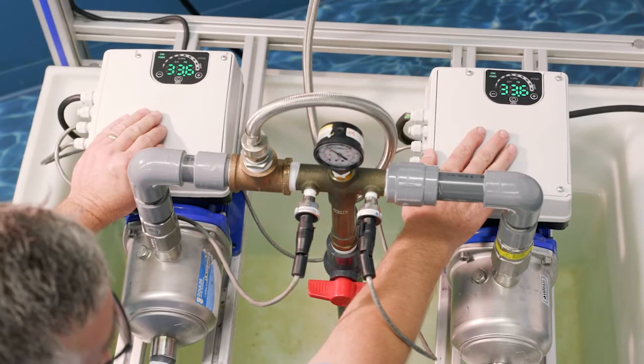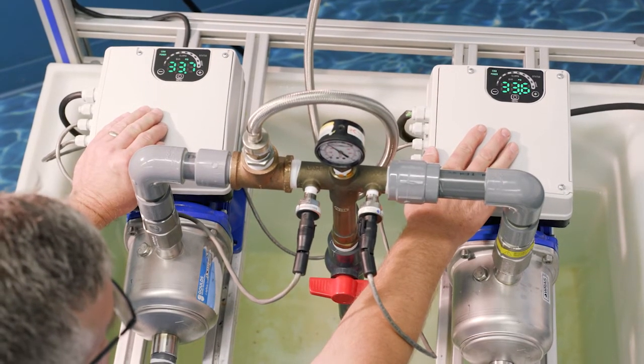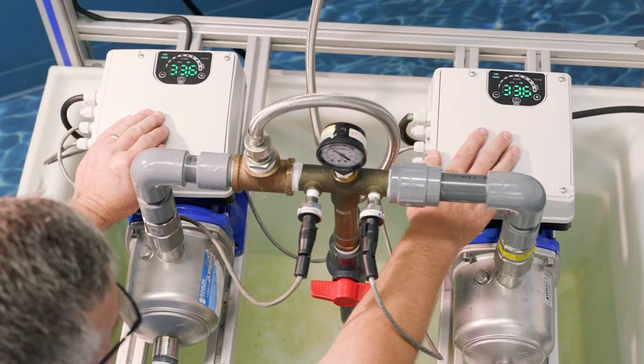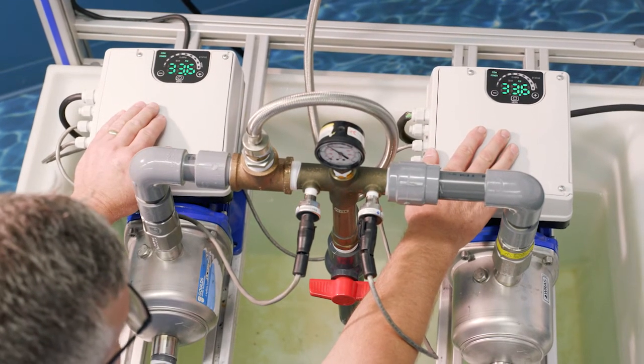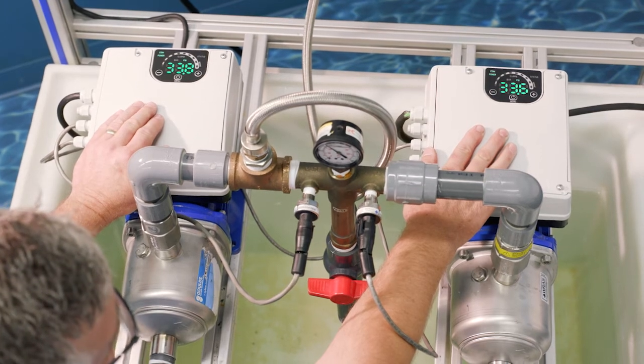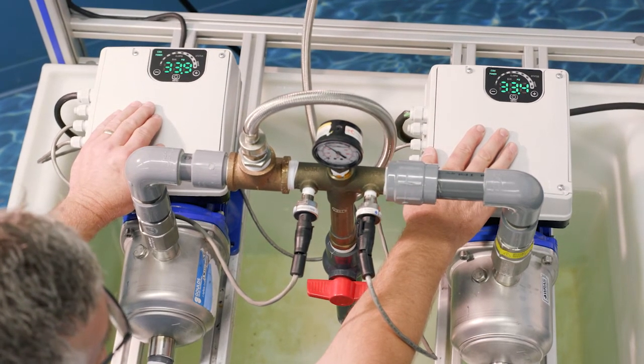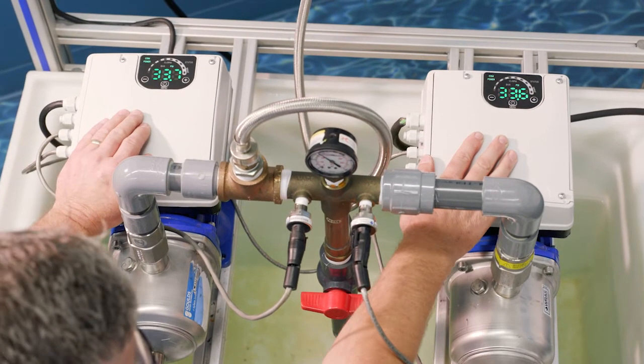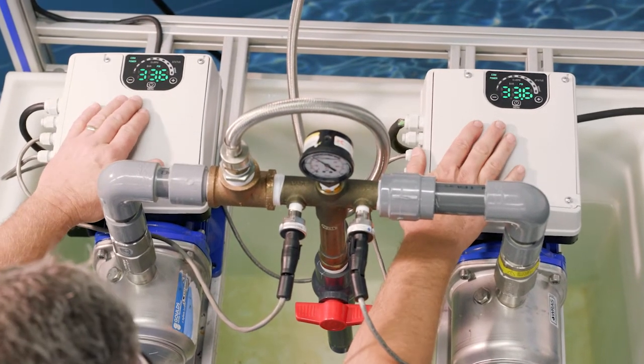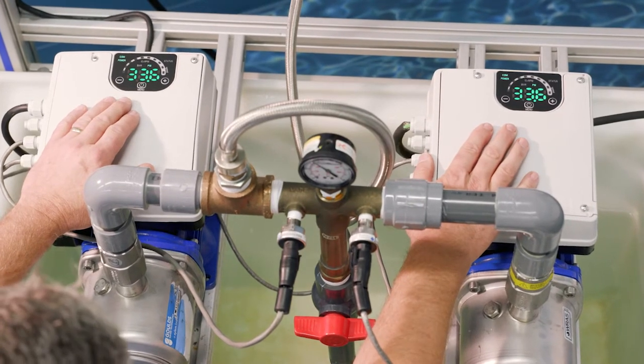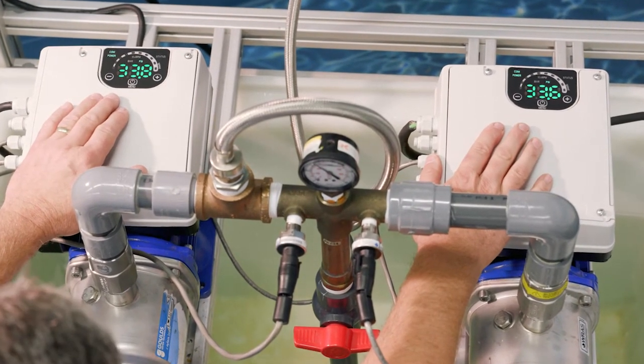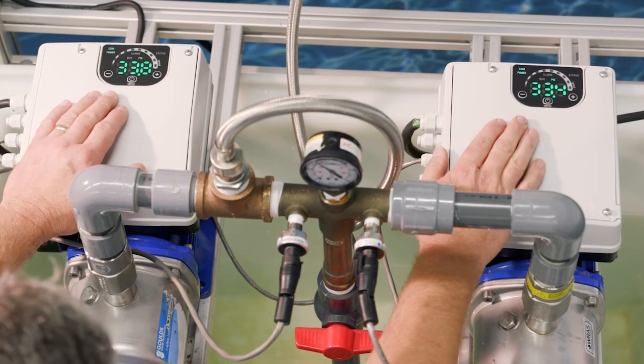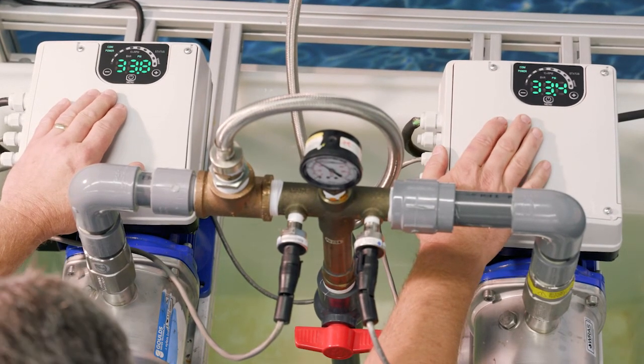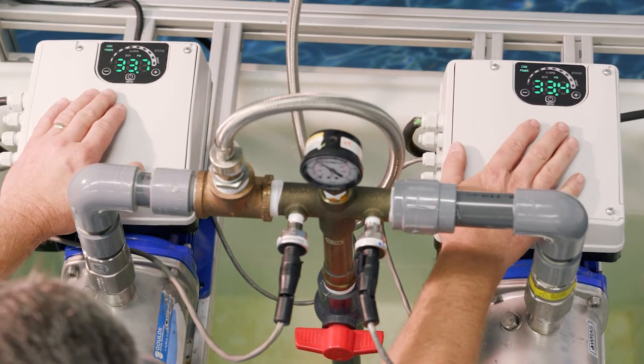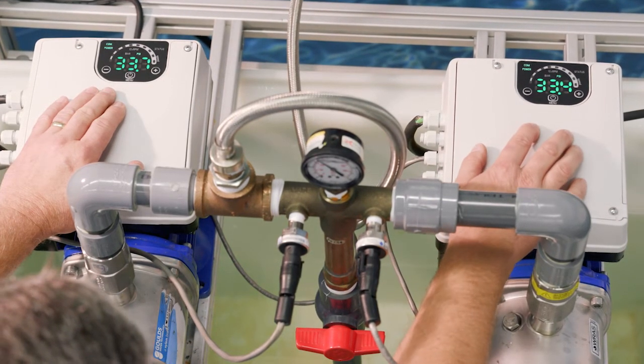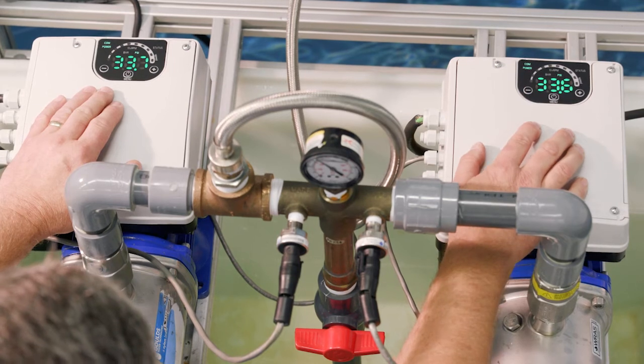That was multi-pump synchronous. Your other option in a multi-pump operation, again, whether it's 2 pumps or 3 pumps, is to go with the NSE, serial cascade. So basically how that's going to work, and we'll set it up, we just have to go into one parameter, the P25 parameter. We'll change that to NSE, and then we'll run it. But basically how it works is, again, let's think about the one on the right as your lead.